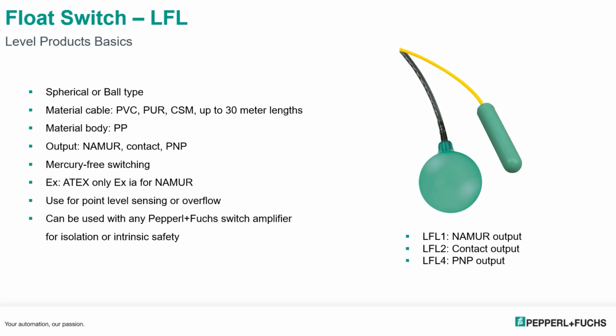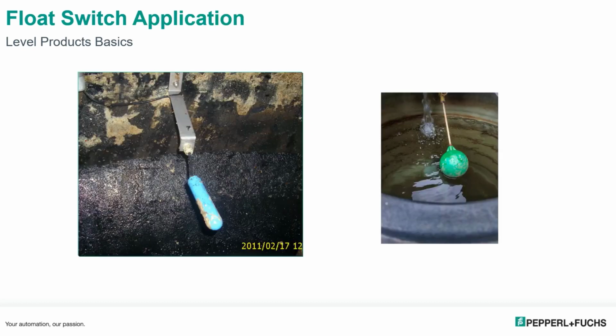They can come with ATEX for the EX ia, which would be your NAMUR output to an intrinsically safe barrier. Very good for point level sensing for overflow conditions. The LFL1s give you the NAMUR output, LFL2s the contact output, and the LFL4s will give you the 3-wire PNP output. Here is an example of a float switch in a wastewater treatment area.